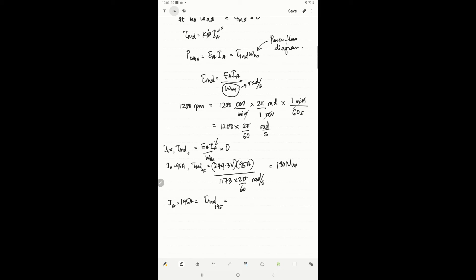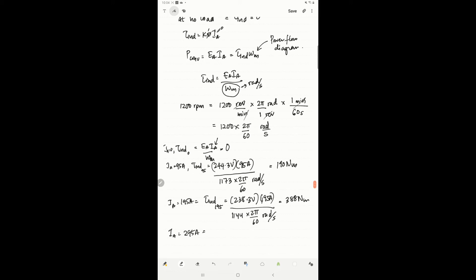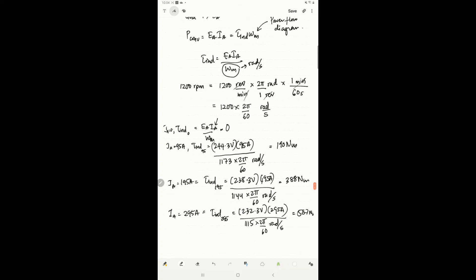When ia is 195 ampere, torque induced equals 238.3 volts times 195 ampere divided by 1144 times 2π over 60 radians per second, giving 388 newton-meters. When ia is 295 ampere, torque induced equals 232.2 volts times 295 ampere divided by 1115 times 2π over 60 radians per second, giving 587 newton-meters. We now have all the torque and speed values.